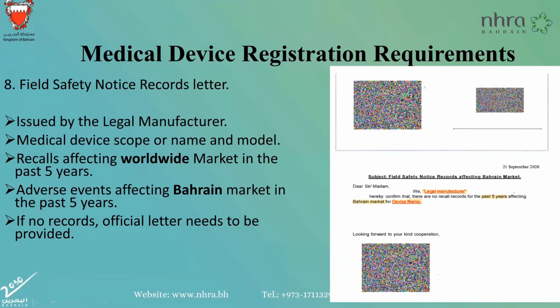The 8th requirement is the field safety notice record letter. What is meant by field safety notice are the adverse events and recalls. Also, for this requirement, an official letter issued by the legal manufacturer needs to be provided, and it should list the devices and their recalls worldwide in the past 5 years, as well as the adverse events affecting the Bahrain market only in the past 5 years.